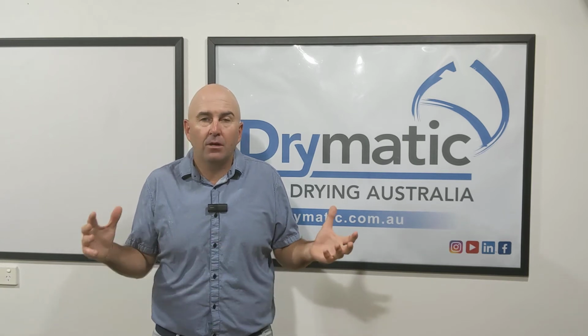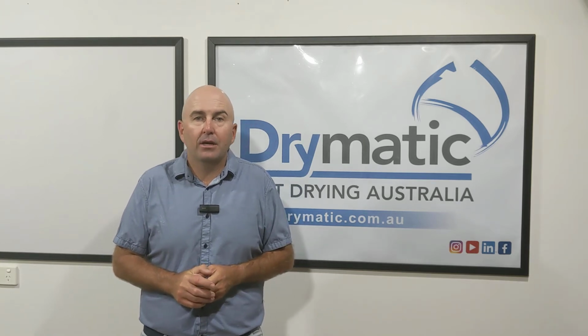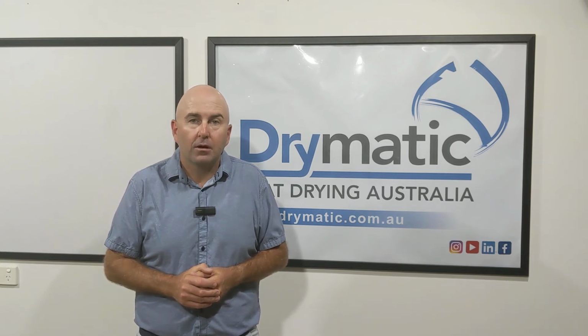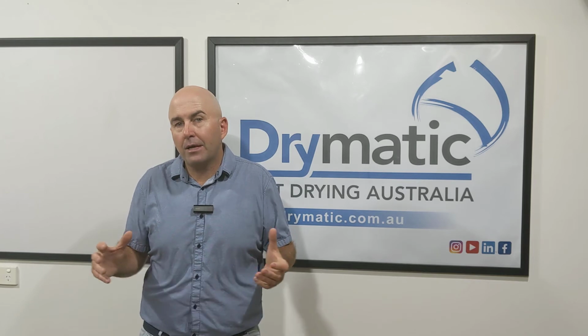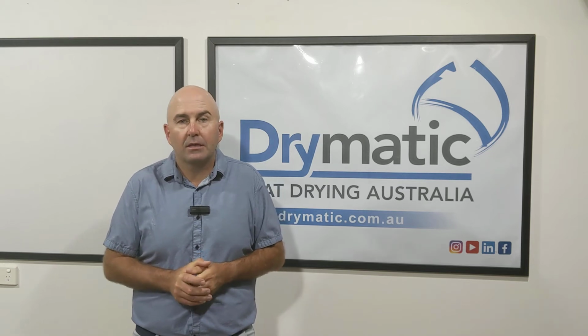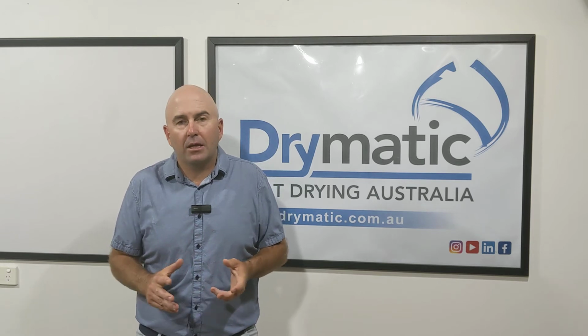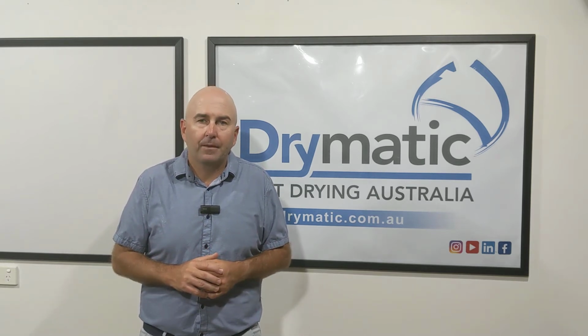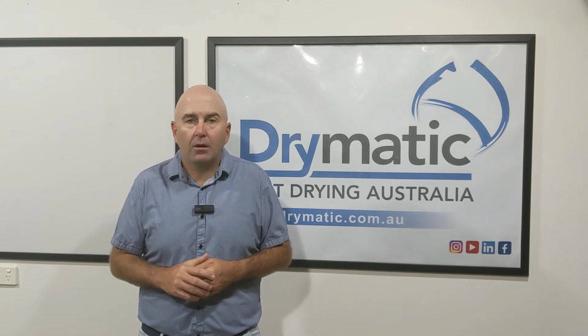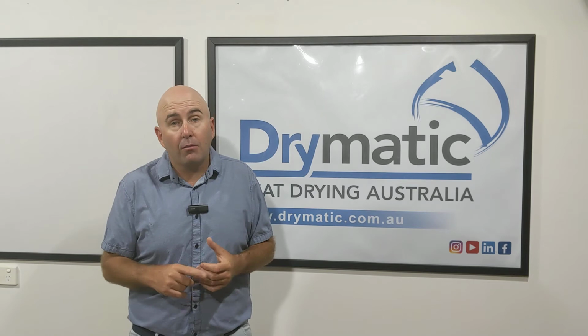So if you looked at a class 3 and say 100 cubic meters, you're going to need at least 2 of those dehumidifiers, right? If you looked at something at about 300 cubic meters, you're going to look at about 6 dehumidifiers, as per the IICRC guidelines, the S500 standards. So I need this much equipment. Yet the Drymatic 2 will do 2 air exchanges for that size area. As long as you do a minimum of 2 air exchanges with the Drymatic 2, I can get away with one Drymatic 2.